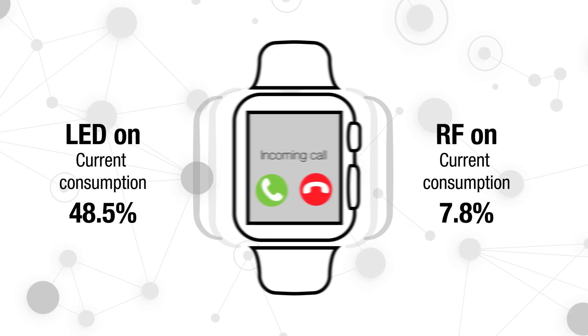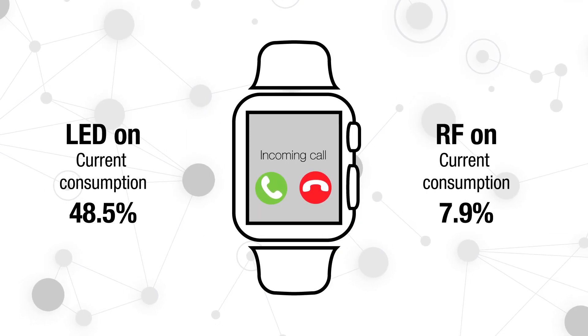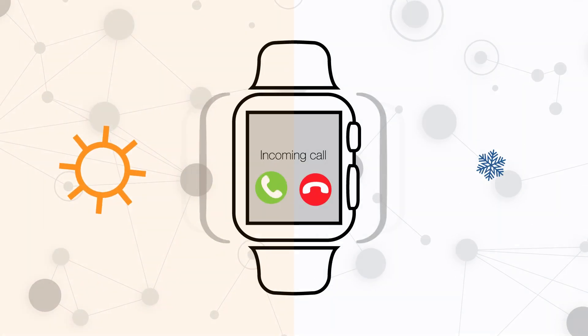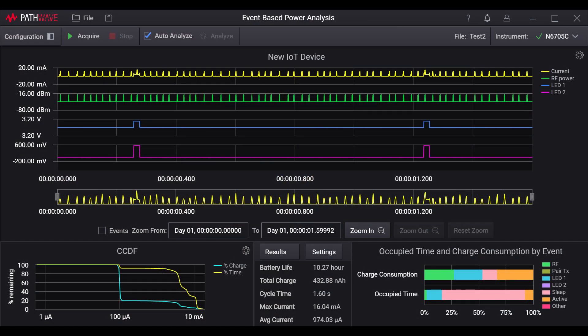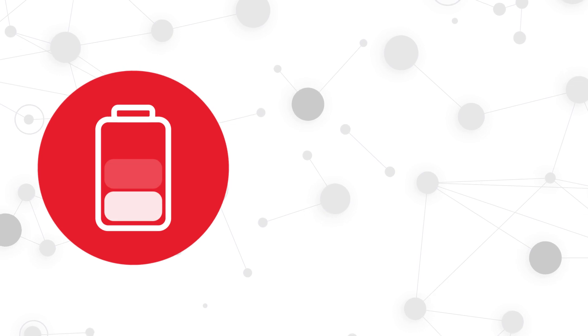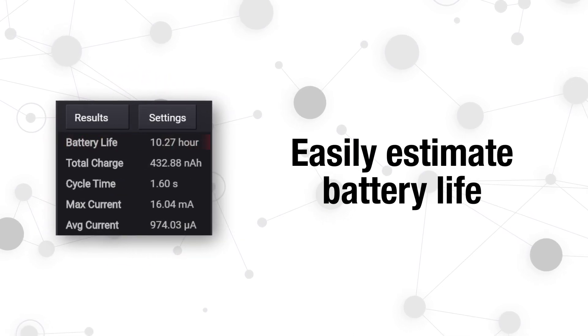For example, simulate a one-day operation in varying climatic conditions using an environmental chamber where the average current consumed will be automatically calculated. The software will then estimate the battery runtime expectancy.